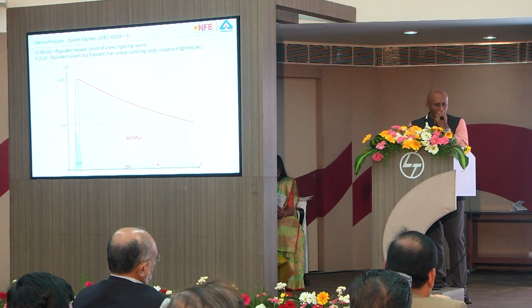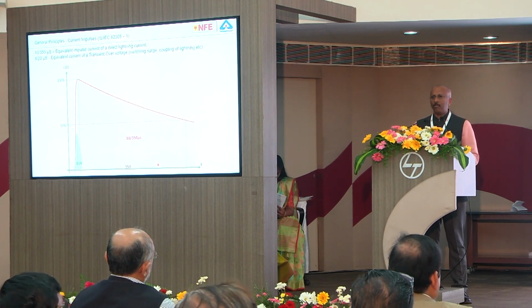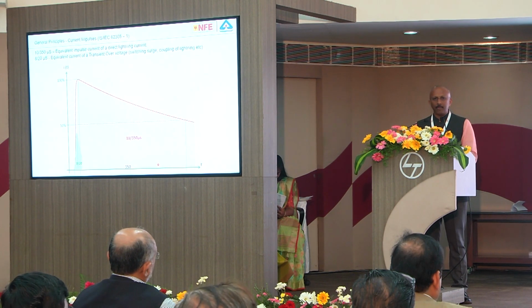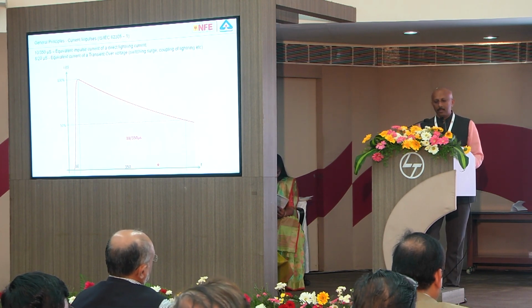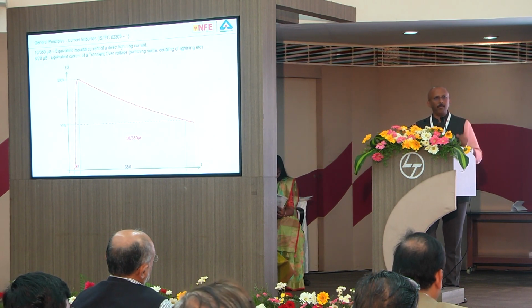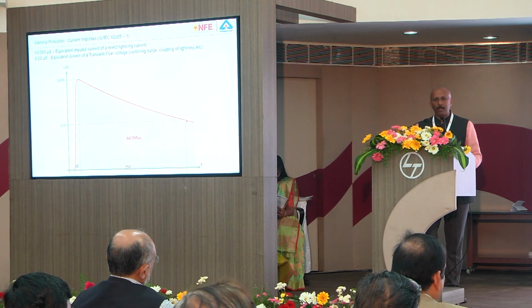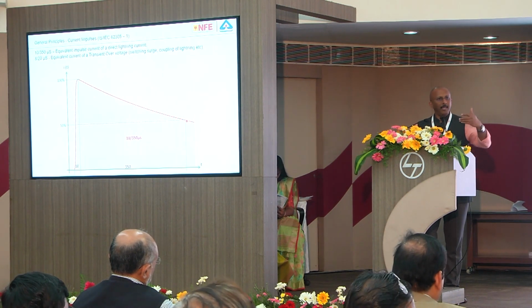So the first question which people always ask is, what is this 10 by 350 and 8 by 20? Sometimes this is also a serious point of discussion. 10 by 350 is very big, and it may be dangerous. 10 by 350 is a simple current waveform. The equivalent energy of lightning, a direct lightning impact, if we convert the equivalent energy into a current waveform, the current will look like this. In 10 microseconds it goes to peak and it comes to half value in 350 microseconds. It means not all lightnings are 10 by 350. Lightning can be any value.